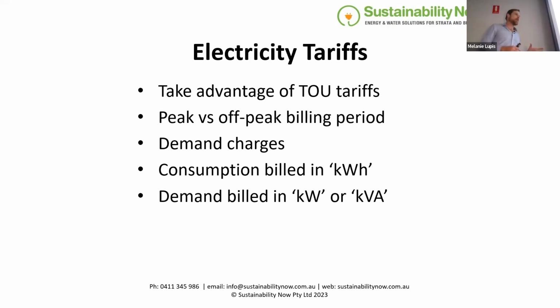So your electricity consumption is billed in kilowatt hours. And I talked about this before, your electrical demand is billed in kilowatts or kVA. There's a little weirdness there: if you're using between 100 and 160 megawatt hours, you're billed in kilowatts for demand, so power factor is kind of irrelevant to you financially. But for the bigger sites over 160 megawatt hours, you're billed in kVA, when power factor is definitely of interest to you financially. Although Ausgrid has a network standard that says you shouldn't have a power factor lower than 0.9 at the main, at the supply point to the site.